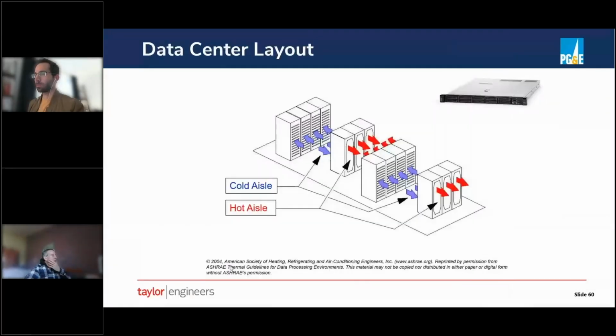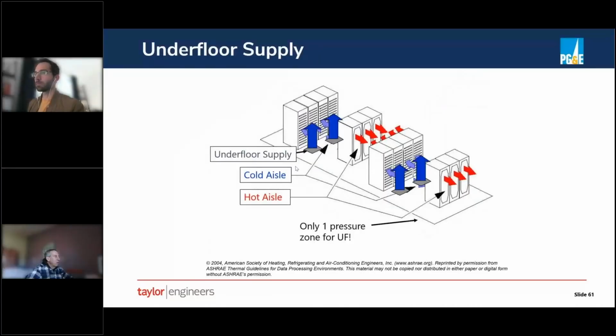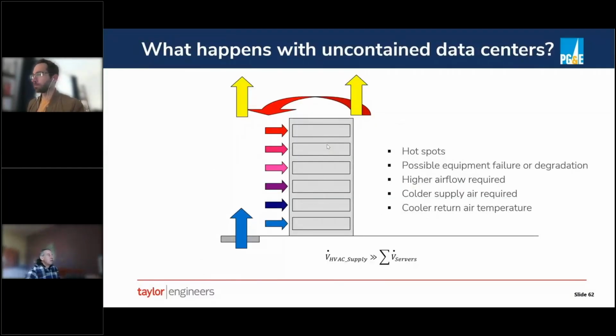Okay, so containment. We showed this before. You want your computers set up in hot and cold aisles. The sort of original computer rooms or data centers were typically raised floor, where the air was coming out of the floor in the cold aisles. And originally data centers didn't have containment, and what would happen is that you would have hot spots at the top of the racks.